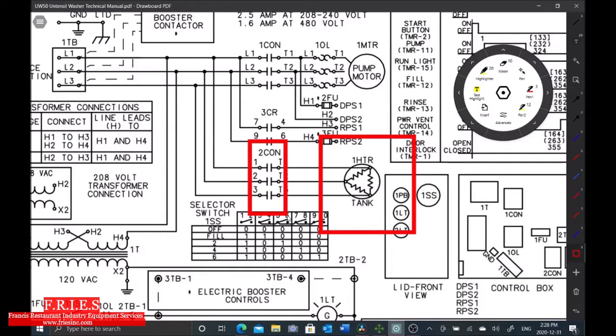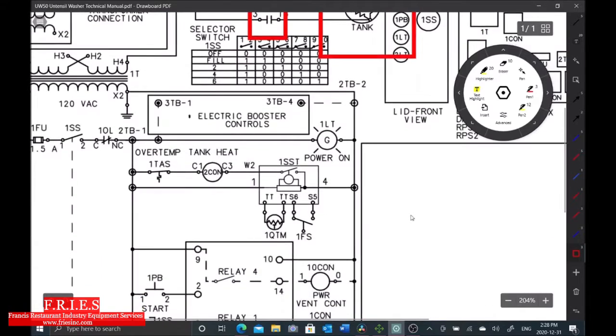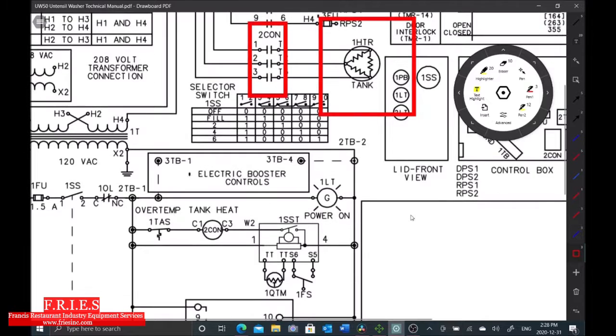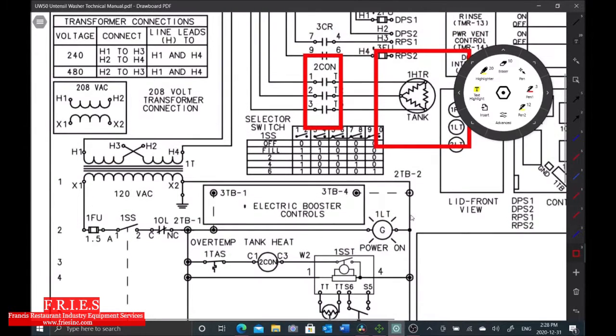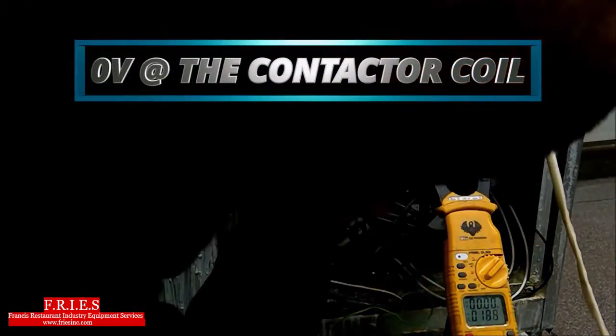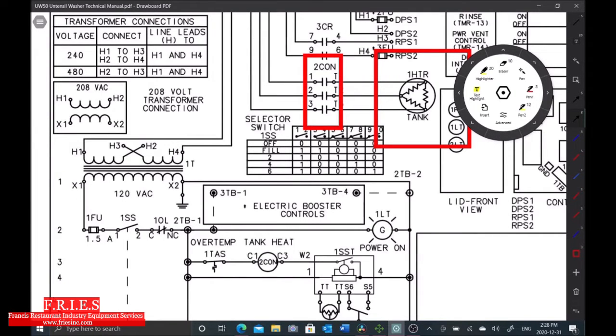So the next step now is what closes the contacts. In this case, it's the contactor coil. This is labeled as 2-con or 2-contactor. So the next thing we're going to look for is the coil symbol, which is a circle with 2-con in it. And that's labeled right here. Okay. So the next thing we're going to do is test for power at this contactor coil. Alright, so I'm going to go test this contactor coil. Sorry, the angle's pretty bad here. I am getting 0 volts at that coil. Alright, I do not have power at the contactor coil.